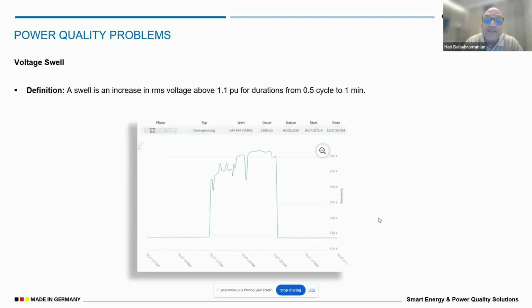Or the swell here, which is going up for 1 second, yeah, 1,000 milliseconds, up to a voltage of 284. This is also not good, and the previous one is also not good for us. So this is how we can understand sags and swells. Sags and swells are most common in our networks when the grid is weaker, when the transformer is fully loaded or working to its capacity, and a very small short-term increase in load or the starting of a motor can also create a sag in the network.